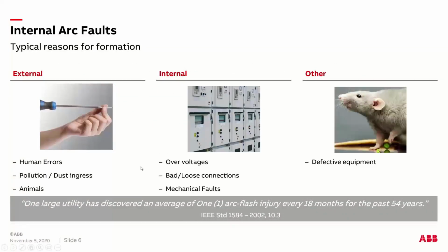So internal arcs, it's very well known in the industry over the past 30, 40 years, maybe 50 years, right? So it could originate due to external factors such as human error or pollution accumulation or dust ingress, just because of the environment where the equipment has been installed. Sometimes animals creep into the equipment and create arc flash over the different phases, right? And in other cases, you can have bad or loose connections on your cable connections, which over a period of time can lead to an arcing event, right? So these are some of the factors that could lead to an internal arc within your equipment.